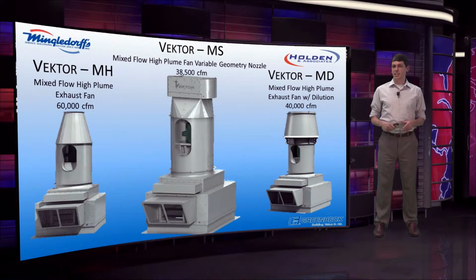The benefits of the M series of fans is the bifurcated housing, which completely isolates the drive components from the airstream during maintenance. The M series can also be used on an ERS plenum, Greenheck's energy recovery plenum, utilizing a coil design that can completely isolate the exhaust airstream from the supply airstream. You'll also see the Vektor MS, which again has that variable geometry discharge nozzle, which we'll soon get to.